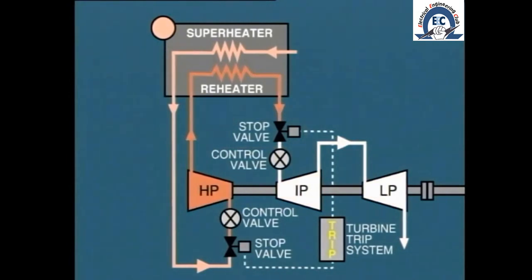If there were no reheat stop valves fitted, then the large amount of steam that is contained in the reheat piping and reheat tubes in the boiler would continue to flow to the reheat turbine for a short period of time and cause overspeed. In other words, we would have no control over this relatively large quantity of entrained steam. The reheat stop valve prevents this from happening.